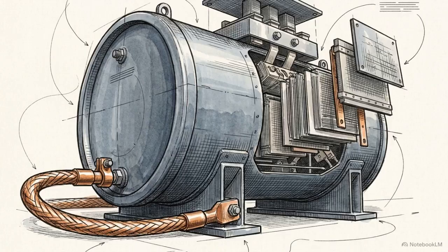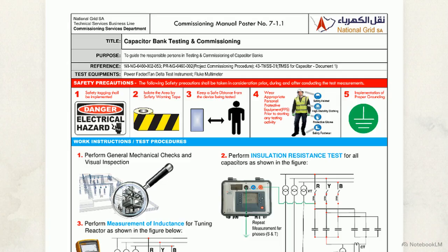The foundational safety axiom for the entire procedure is that a capacitor holds a lethal charge until it is mechanically grounded and verified. This banner details the 5 mandatory safety precautions. The area must be tagged and isolated, personnel must keep a safe distance, wear arc flash PPE, and implement proper grounding before any measurements begin.